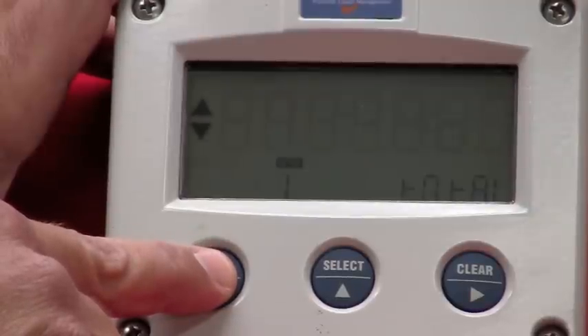If I hit the arrow over again, you'll see I'm back to the total menu. That's the complete programming of this flow rate indicator. To jump out of programming, there's two ways to do it. One is to let the unit time out, which takes two minutes before it will go back to the run mode. Or a quicker way is just hold in your programming key for two seconds and it will return back to the run mode.